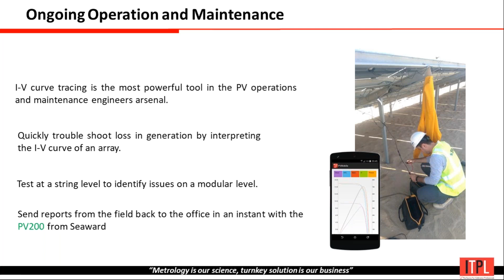inverters, and suppose one of the inverters has 7 combiners connected, and each combiner has 8 strings. We can test each string properly at a particular radiation, suppose 700 watt per meter square and temperature around 40 degrees, and having tested 8 strings, we can conclude that in one of the strings I'm getting less power and less current and everything as compared to the other 7. So in that case we have to go to individual module testing, and we will be able to identify exactly which panel is not performing as per expectation. After that, we have to call the module manufacturers, or do thermal imaging. That is a further process, but this is the quick troubleshooting solution with the help of these kinds of tools.